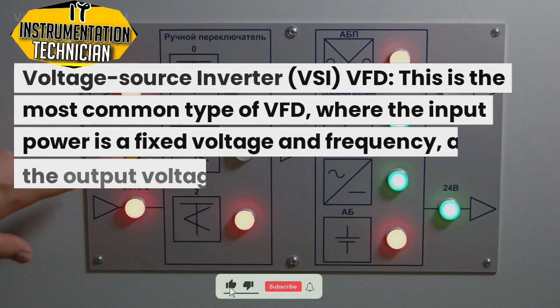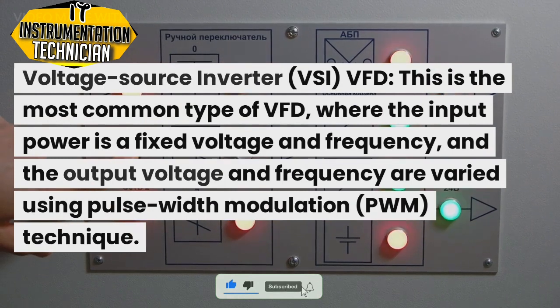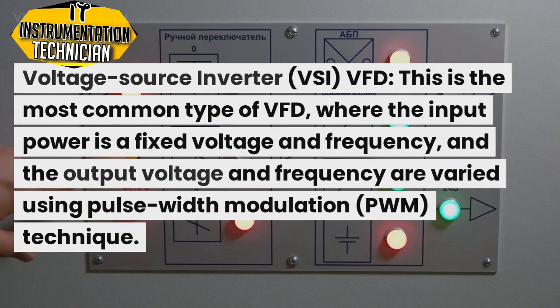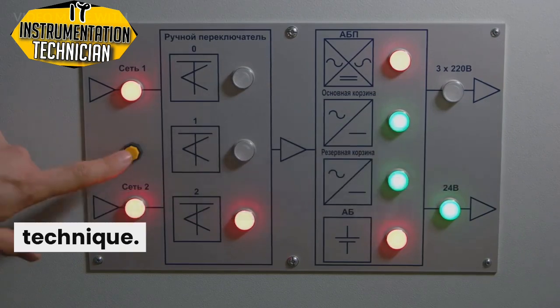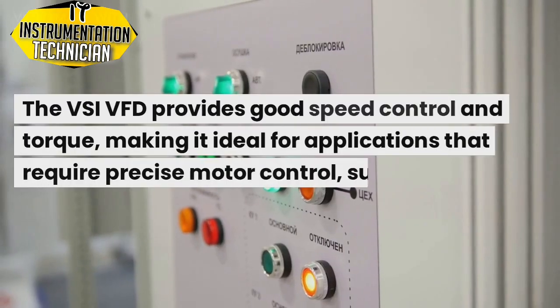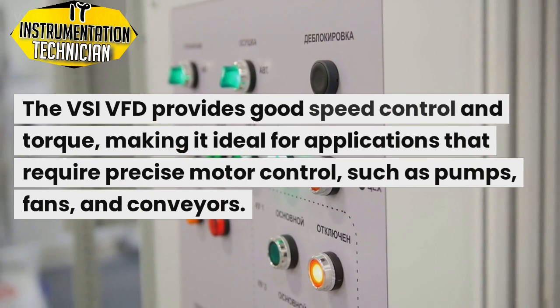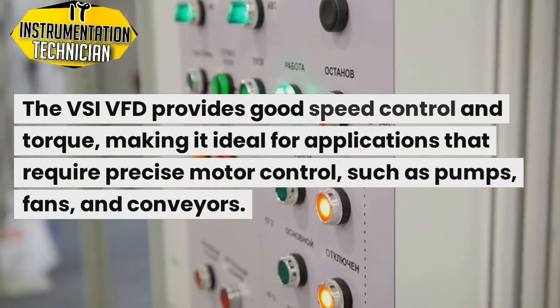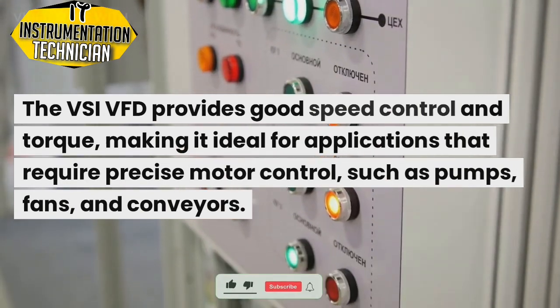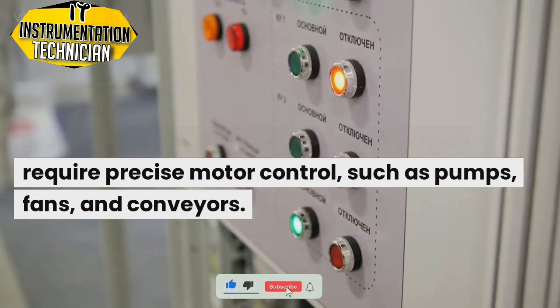They are Voltage Source Inverter (VSI) VFD. This is the most common type of VFD, where the input power is a fixed voltage and frequency, and the output voltage and frequency are varied using pulse width modulation (PWM) technique. The VSI VFD provides good speed control and torque, making it ideal for applications that require precise motor control, such as pumps, fans, and conveyors.